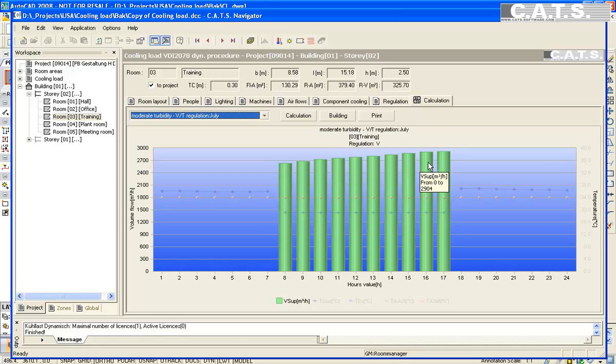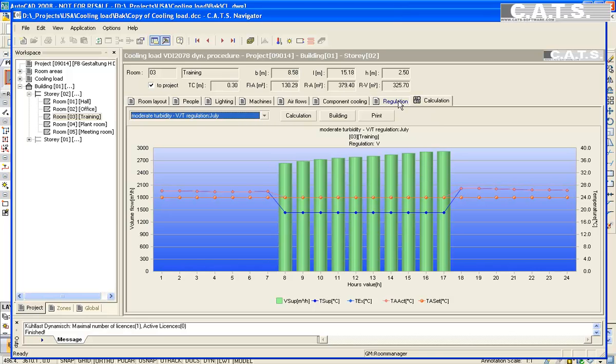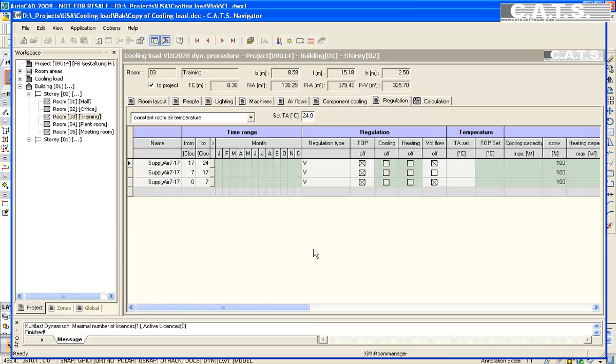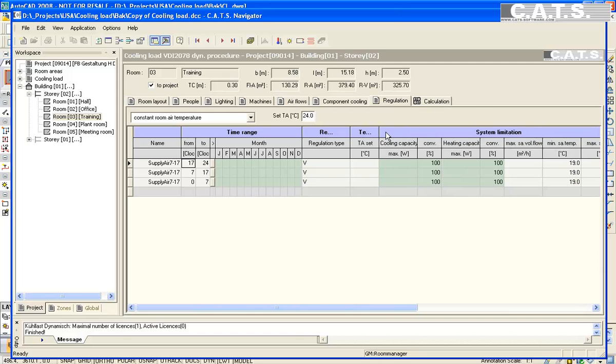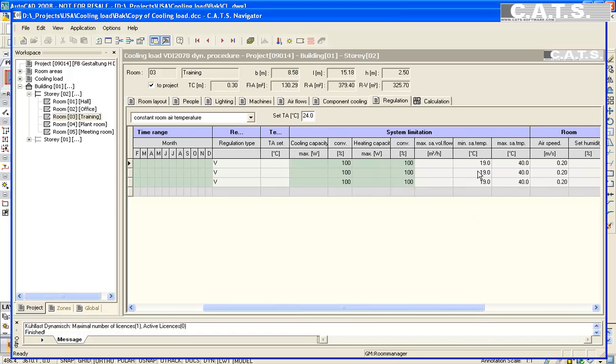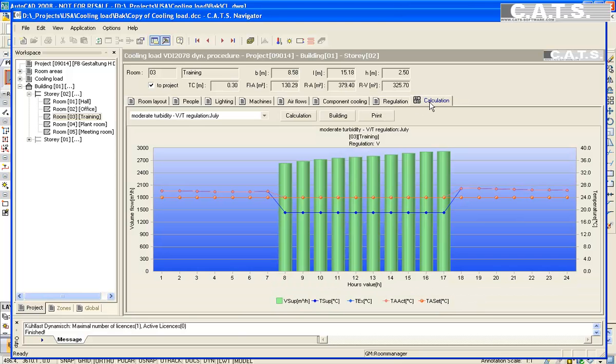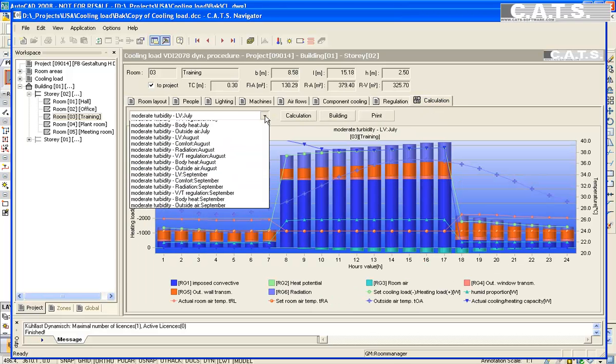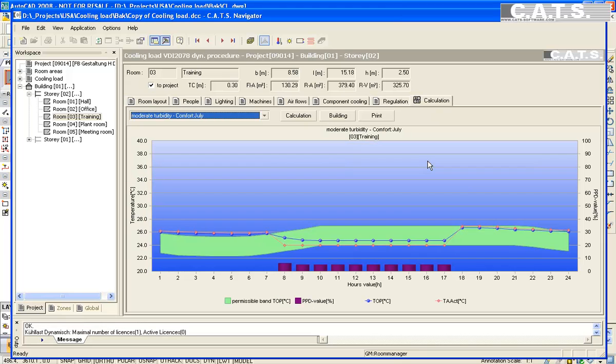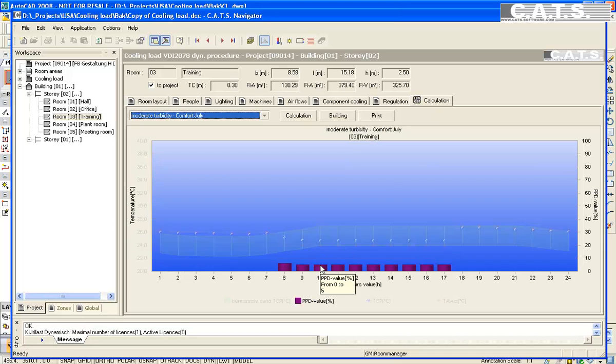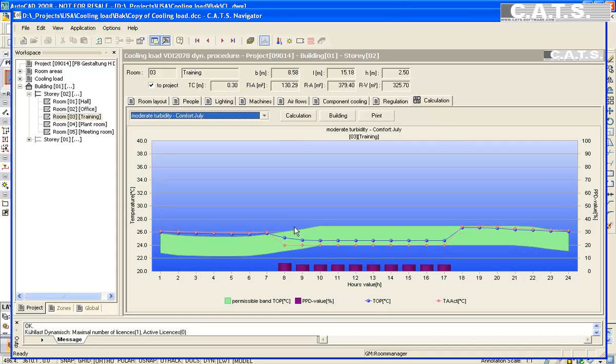During the occupied period, the room temperature equals the setpoint. The air supply is at 2900 cubic meters per hour. We will now change the supply air temperature from 19 degrees to 20 degrees. This will now require 3600 cubic meters per hour at a requirement of over 20%. With the flexibility and ease of input with the CAT's cooling load calculation, the designer can easily change system parameters and view the impact of his changes. Checking the comfort zone we are within our boundaries.